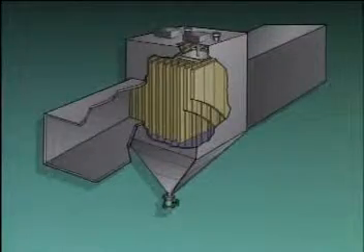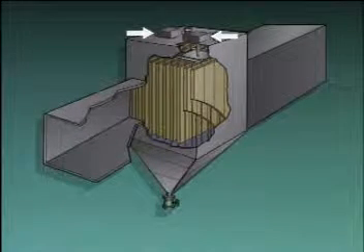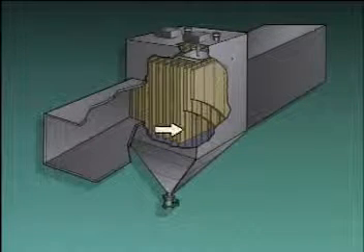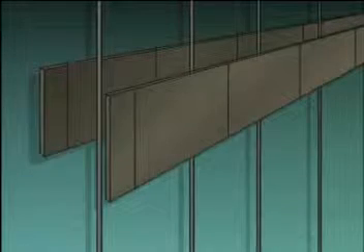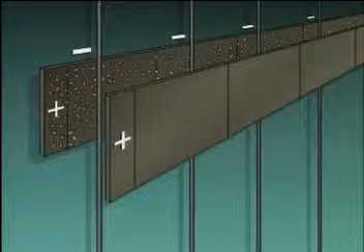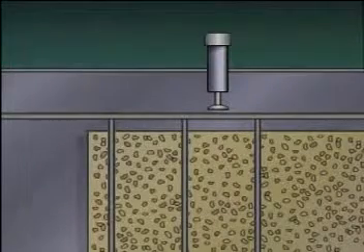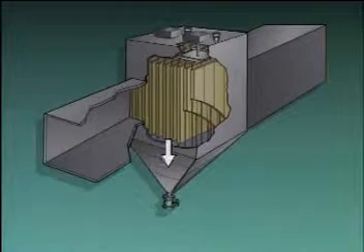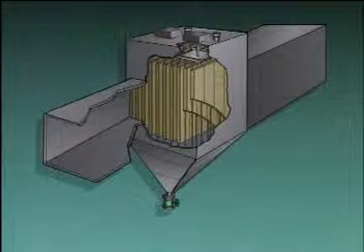Electrostatic precipitators remove particulates using an electrical charge. An electrostatic precipitator has several power sources that create a positive charge on a series of metal plates and a negative charge on a series of wires located between the plates. As the combustion gases pass through the precipitator, the particulates pick up a negative charge from the wires and are attracted to the positively charged metal plates. Devices called rappers are used to physically jar the collected particulates loose from the plates. The particulates slide into a collection hopper in the bottom of the precipitator. From there, they can be removed from the system.